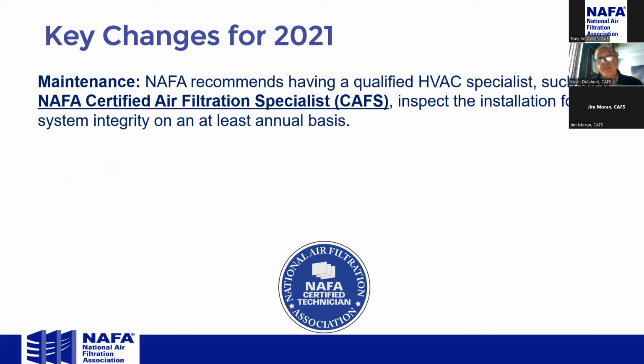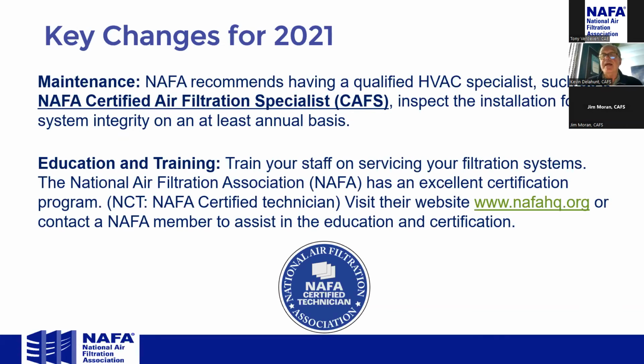Key changes to the NAFA guideline in 2021: maintenance was one of the big ones. We recommend having a qualified specialist, a NAFA certified air filtration specialist, inspect the installation for system integrity on at least an annual basis. Get that third-party person in, have a look at the system to try to identify any areas where your system's not living up to the performance that you paid for. So bring in an outside person. The CAFS are specialists in air filtration, and if we're looking for bypass, it can be found.